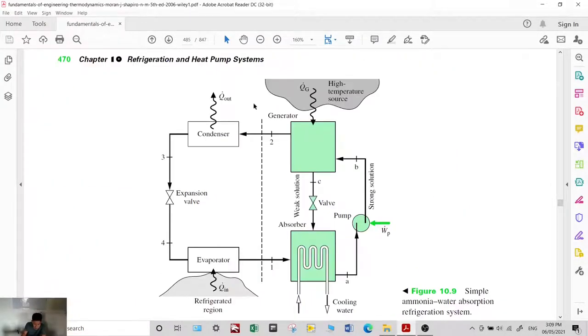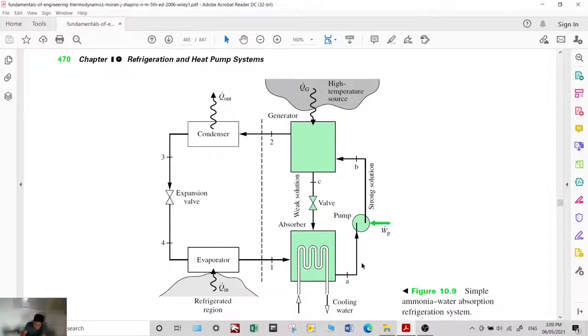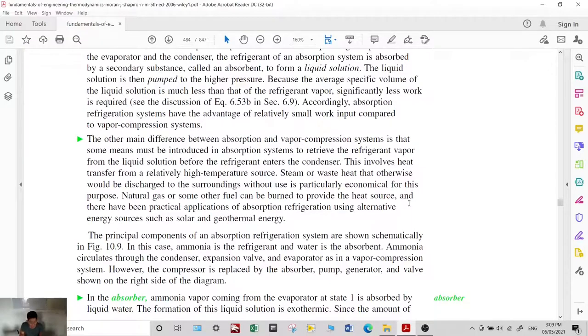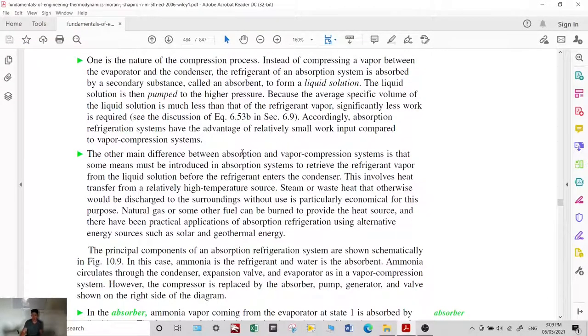In the absorption refrigeration system, the components include an absorber, pump, valve, and generator — replacing the compressor. The other main difference is that some means must be introduced to retrieve the refrigerant vapor from the liquid solution. This involves heat transfer from a relatively high-temperature source in the generator.